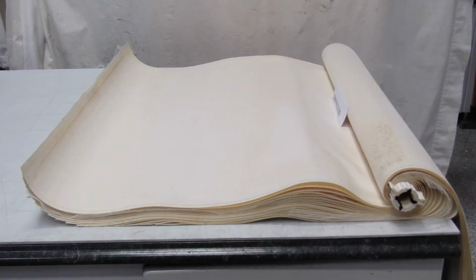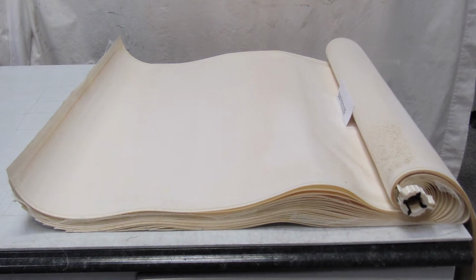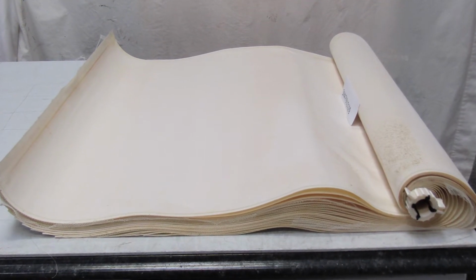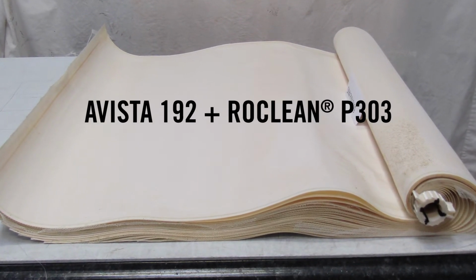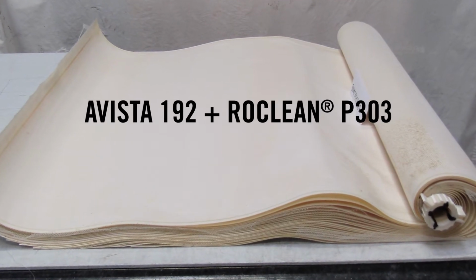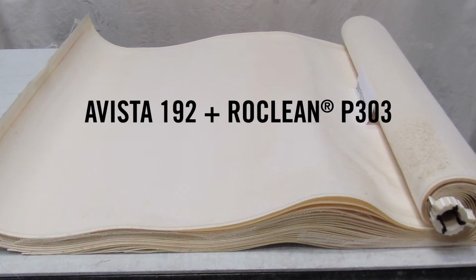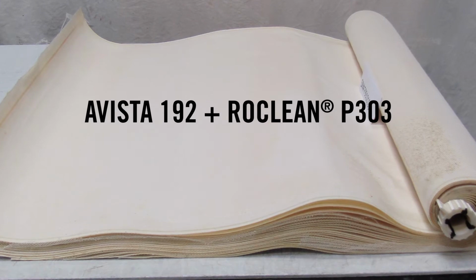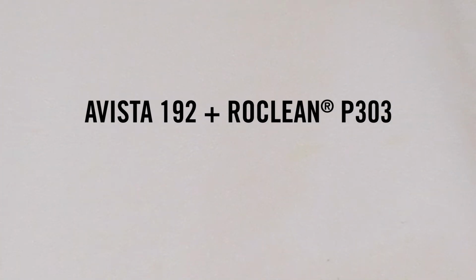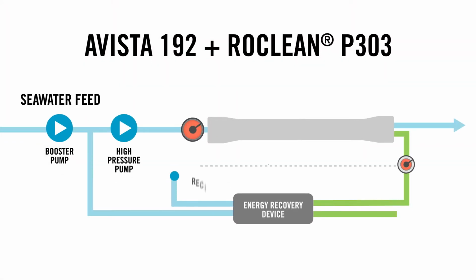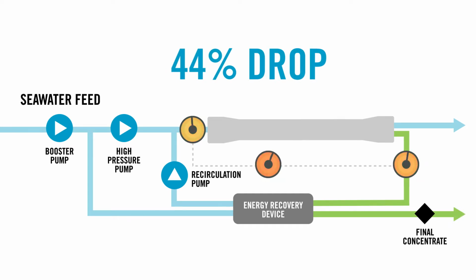Through testing, we identified that a targeted high pH cleaner, Avista 192, combined with RoClean P303, a low pH cleaner, resulted in a virtually foulant-free membrane surface and demonstrated a 44% drop in pressure.